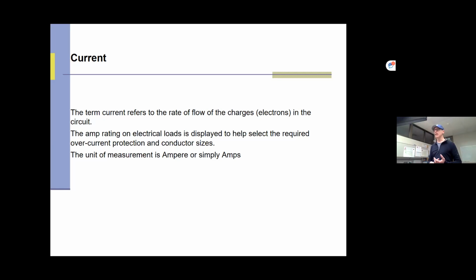If there was a problem with that pump, you guys as operators, it's hard to see what's happening inside that pump. That amperage is going to tell you exactly what's happening in that pump. Because if the amperage gets lower, typically it's meaning there's less work happening with the pump. And that's a good indication perhaps that the impeller in the pump is worn out.